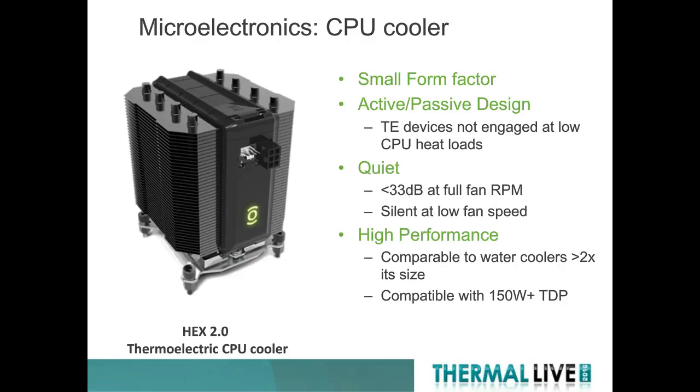That's right. And just briefly building on that, typical passive and forced air systems need to be designed and sized for even the most extreme applications, whereas here thermoelectric devices are providing a space-saving and size reduction capability, because you can start with a small cooler to work passively and as forced air only in that lower power consumption mode, and then utilize the thermoelectric devices in high power mode, and you net save cooler volume for the application.